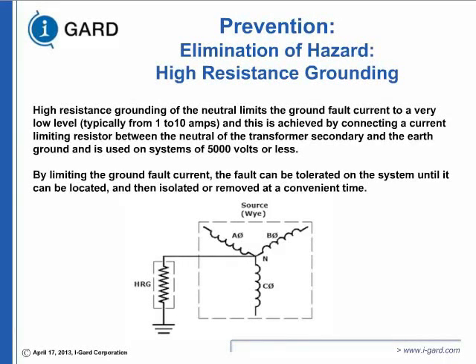Like I mentioned, the concept is simple. It came in the 1950s and 60s from the petrochem industry. Insert a known impedance in the circuit, because all the current has to go back to the source. If you limit the ground fault, you need enough ground fault current to activate your alarm system and above the charging current of your system. That way you limit the damage.